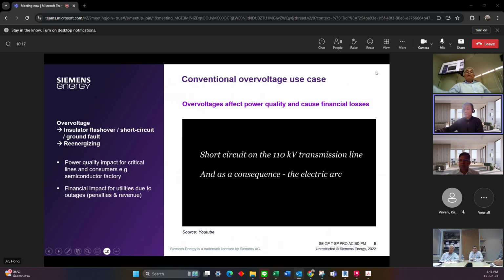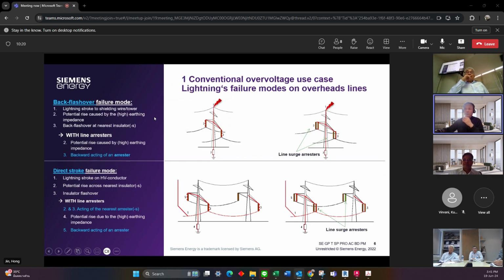And how to summarize the basic reason for the flashover. Flashover will always happen on the insulator, across both ends of the insulator. And the most probable case is the so-called back flashover. And the principle of back flashover is like this: if we have a tower with a very high footing resistance, and when the shielding wire receives the lightning strike, the energy cannot be discharged to the ground in a very short time.